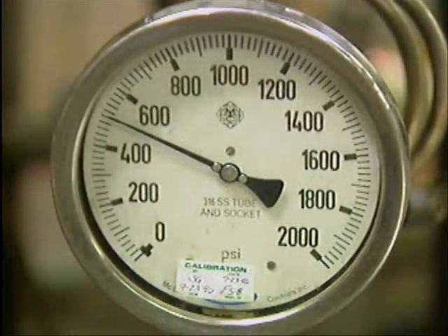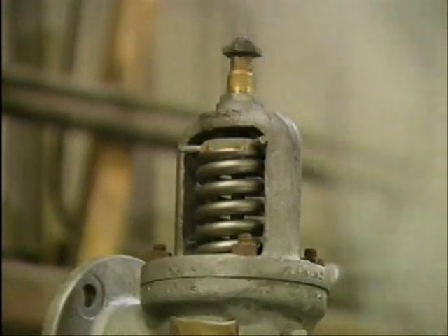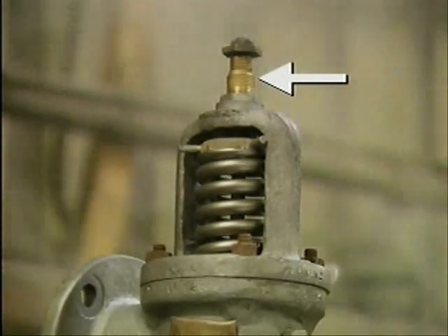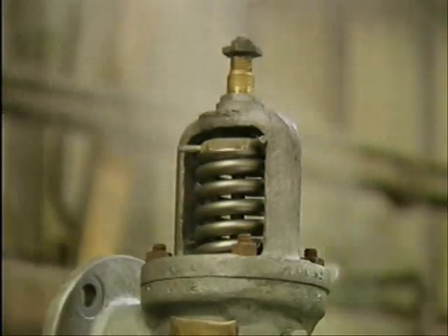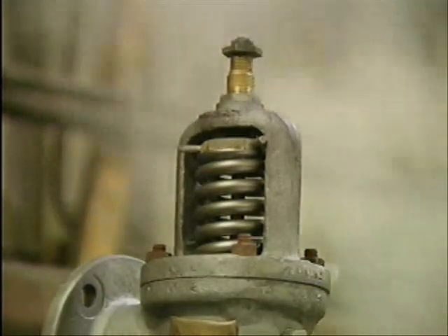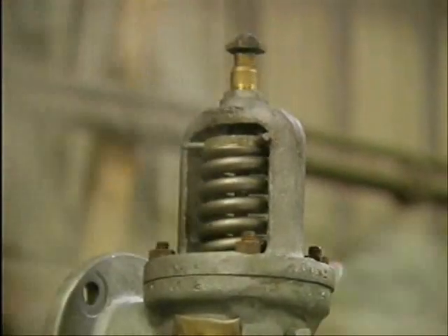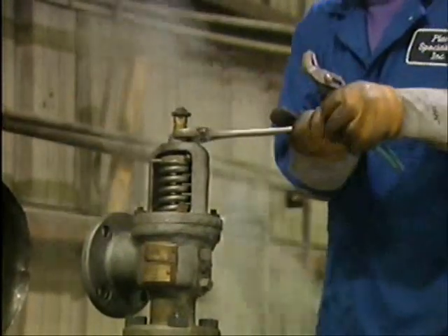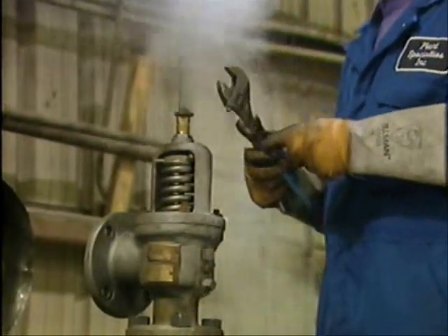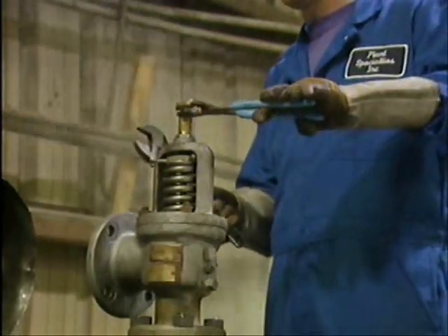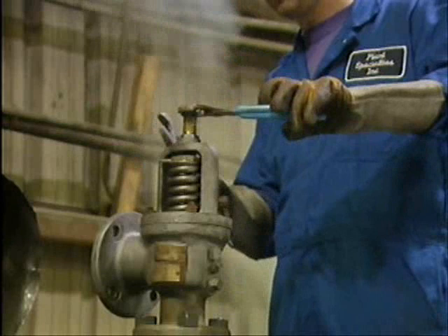The parts will then expand and contract at the same rate during the test. In any case, when you're testing popping pressure, you're checking whether the valve opens when it's supposed to. If it opens too soon or too late in relation to the valve's set point, you must make adjustments. For this huddling chamber safety valve, you make set point adjustments by turning the compression screw. But before you can do that, you must lower the pressure so that there's no chance of the valve opening accidentally while you're working on it. You must also break the lock nut free.